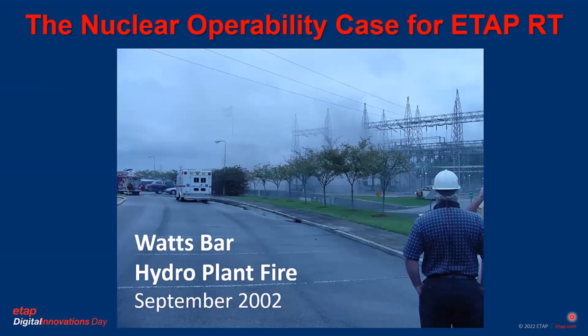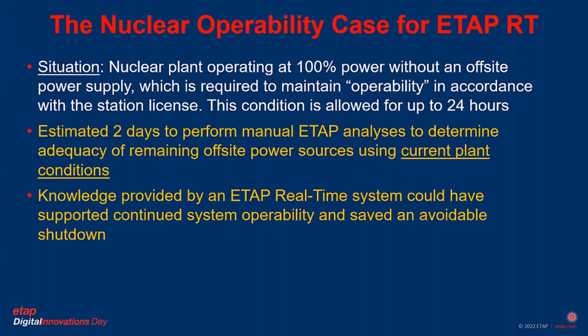There's also a nuclear operability case for having an ETAP RT system, and I'm going to use a case study, an event that happened at TVA at our Watts Bar nuclear plant. The nearby hydro plant had a fire in September of 2002. So the situation there was the nuclear plant was operating at 100% power, again, without an adequate offsite power supply, which is required to maintain what we call operability, which really just means we're operating in accordance with the station license.